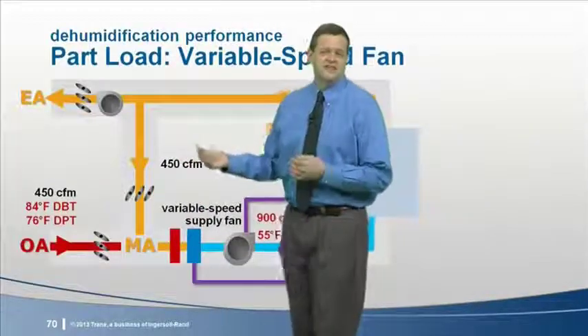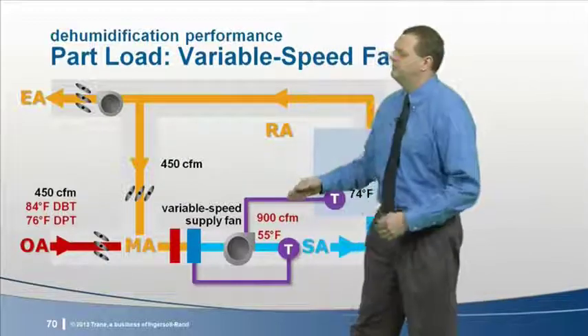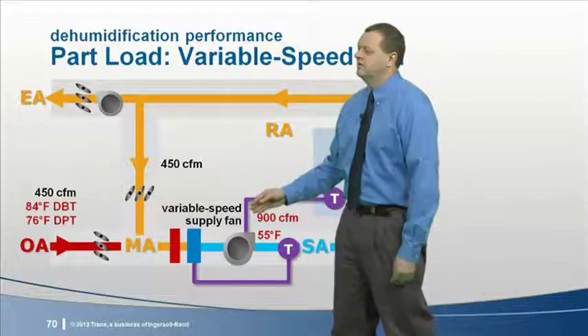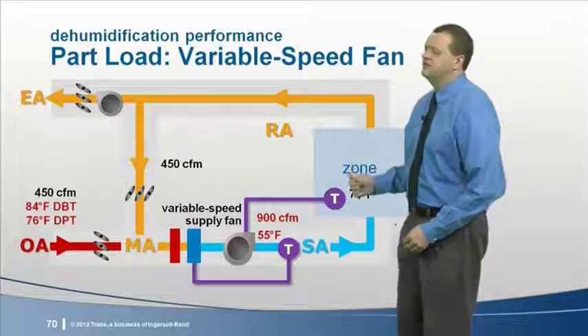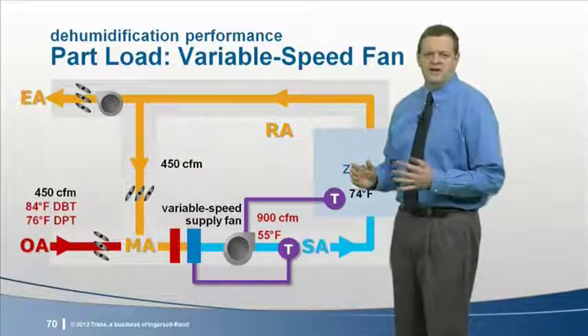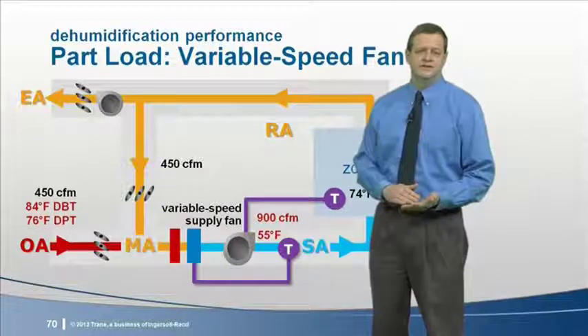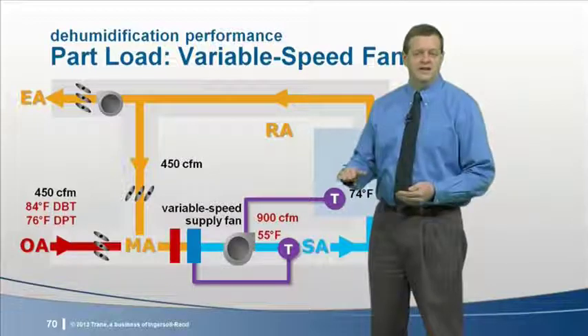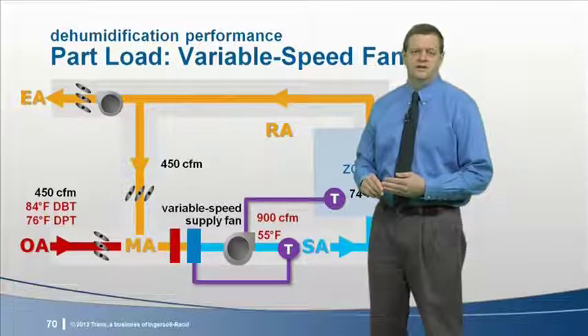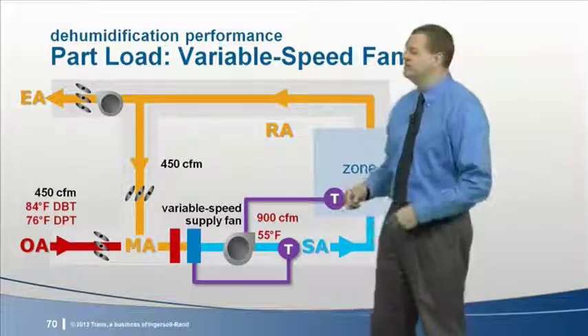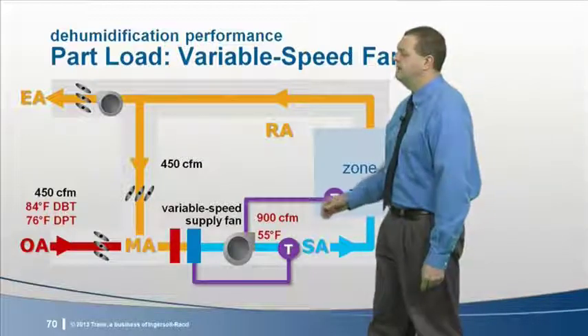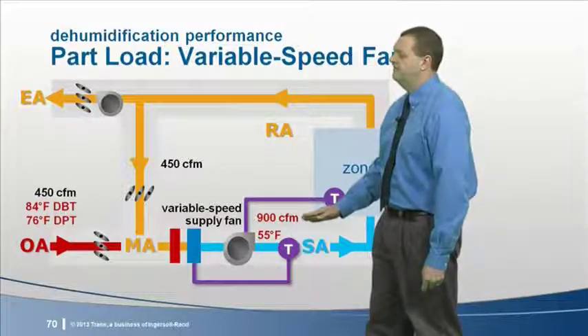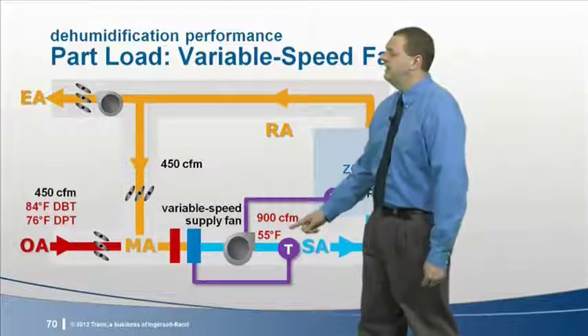Now let's consider the same example, but using a system with a variable speed fan. When the sensible cooling load in the zone decreases, this system responds by first reducing airflow delivered to the zone while maintaining a constant supply air temperature. At this same part load condition, supply air flow is reduced from 1500 to 900 CFM, while still delivering the air at 55 degrees.